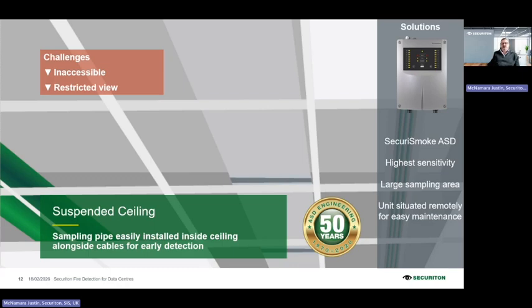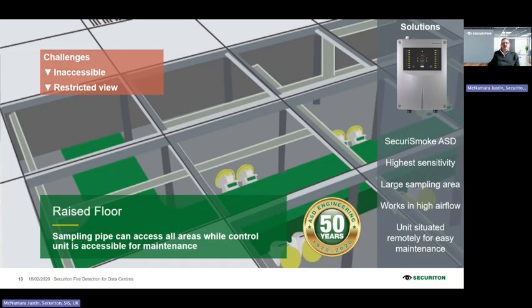So the sensible, smart thing to do is to suggest ASD, aspirating detection. We can design a system with multiple different levels of detection, so we can get staged alarms, and we can do the maintenance from the actual ASD box. We don't need to get into the ceiling void or suspended ceiling itself, or indeed start lifting up floor tiles to get access to the raised floor. It's a really good solution for void areas, ceiling or floor, within any solution, but particularly within a data center where the access is so disruptive, if it's even possible, quite frankly.